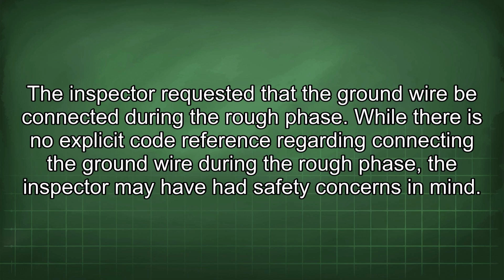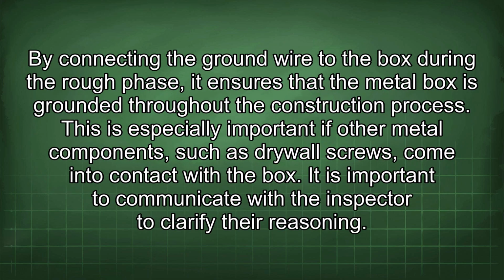While there is no explicit code reference regarding connecting the ground wire during the rough phase, the inspector may have had safety concerns in mind. By connecting the ground wire to the box during the rough phase, it ensures that the metal box is grounded throughout the construction process. This is especially important if other metal components, such as drywall screws, come into contact with the box. It is important to communicate with the inspector to clarify their reasoning.